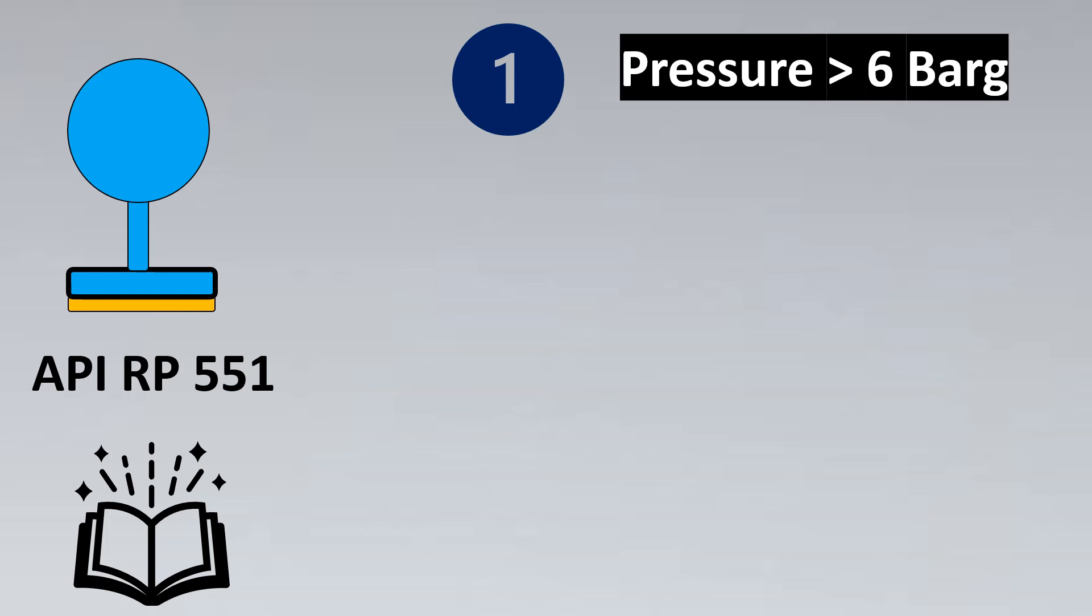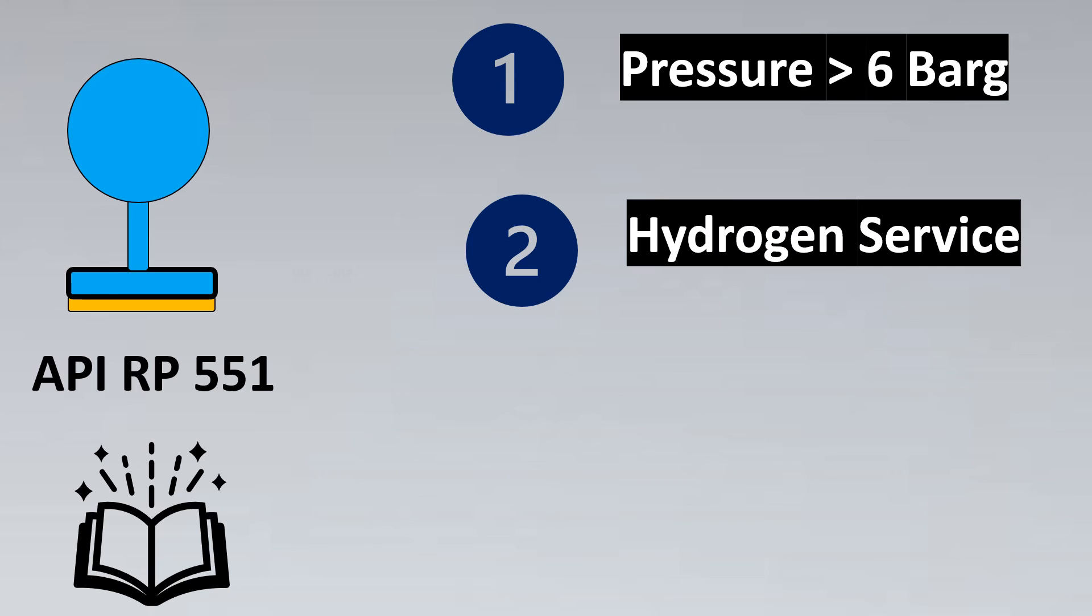Some clients go above 10 bar, some are more conservative and go above 4 bar. It depends. But if there's no client design basis available, you can go with API recommendation of pressure being greater than 6 bar. The second one is quite clear: it has to be hydrogen inside the service. So it's only when hydrogen is there you would have to consider gold plating.